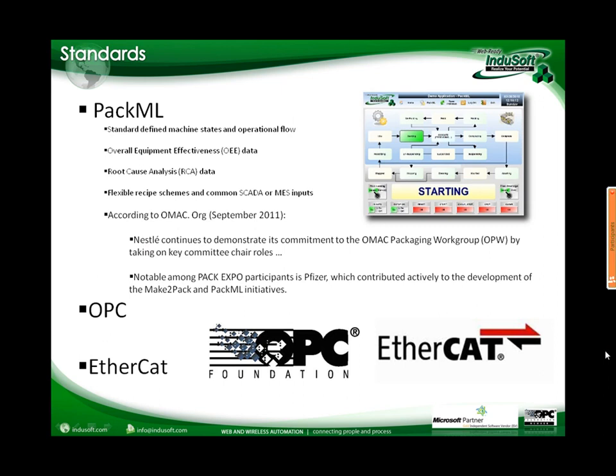We are seeing some standards becoming more popular. PackML is a strong one — it defines standards for machine states and operational flow, covers OEE and overall equipment effectiveness, root cause analysis, and defines a layout for flexible recipe schemas and common data exchanged between the SCADA and the MES. We designed a template application compatible with the PackML definitions, which I'll demonstrate in a few minutes.